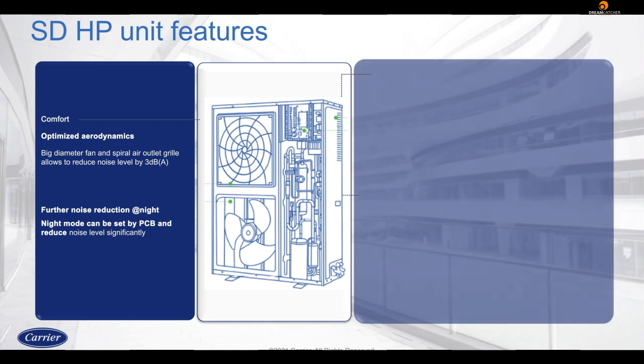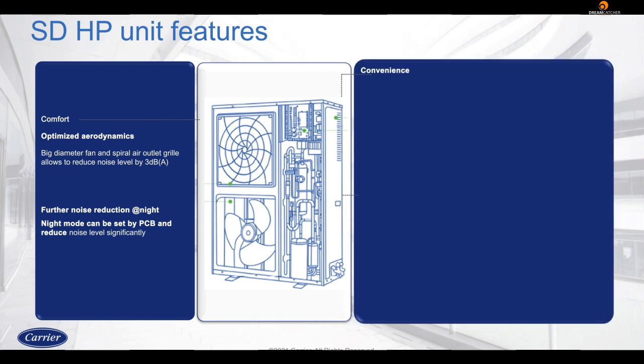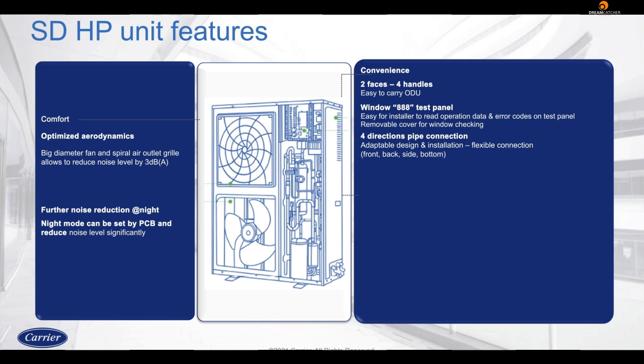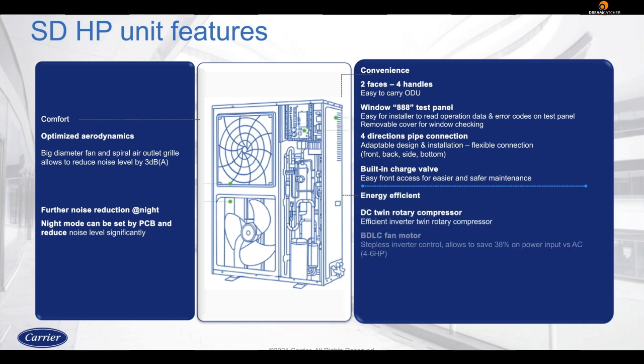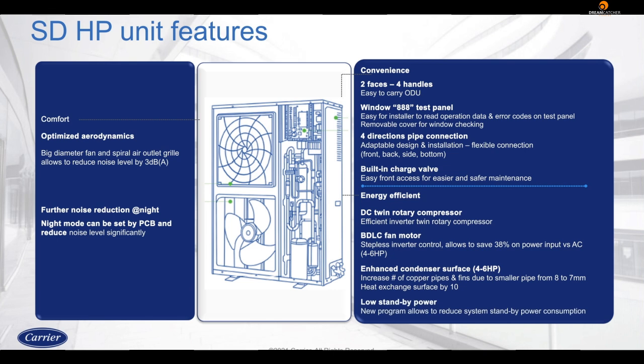The side discharge modules are also easy to install. It comes with 2 faces and 4 handles for ease of carrying. A Window "888" test panel for the operators to read operation data and error codes. A 4-direction pipe connection for flexible connections, and a built-in charge valve for easier access and safer maintenance. It also boasts of DC twin rotary compressors, BLDC fan motors, enhanced condenser surface of 4 to 6 HP, and low standby power, all of which is designed to increase efficiency.